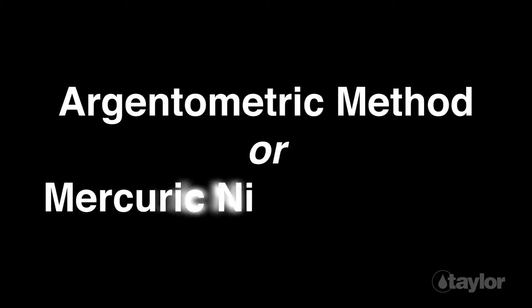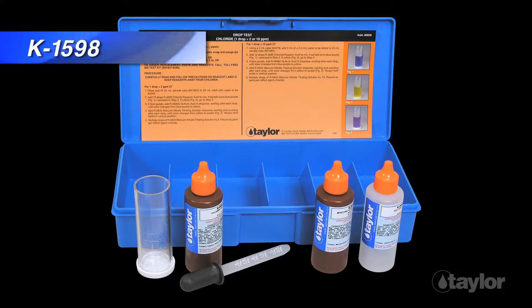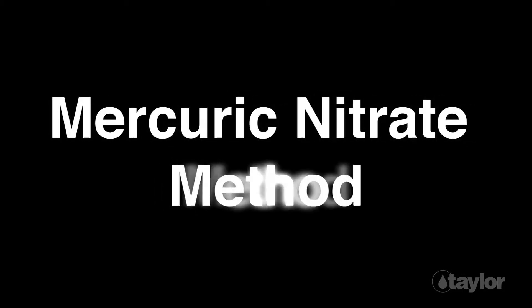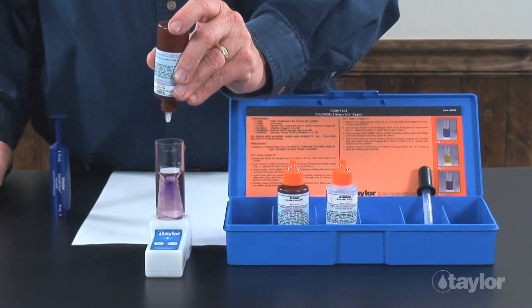Chlorides are determined with a drop test, using either the argentometric method or the mercuric nitrate method. Taylor manufactures both types of test kits. Taylor's K1598, which we will be demonstrating in this video, employs the mercuric nitrate method. This method is preferred over the argentometric method, since the distinct color change signaling the endpoint is easier to recognize.